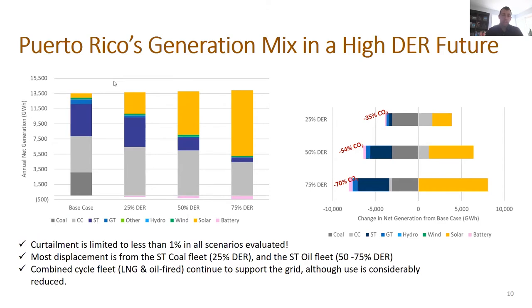Now the last slide showed the inputs into the model, which is installed capacity. This slide shows the annual net generation of the resources. So this is showing across an entire year of operation what resources are producing the energy on aggregate for the entire year. Again, the bar chart on the left shows annual generation by resource type. And as the DER increases from the 25% to 75% scenarios, you can see where the displacement takes place.